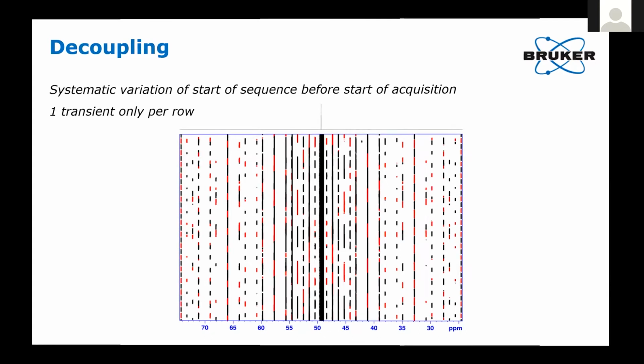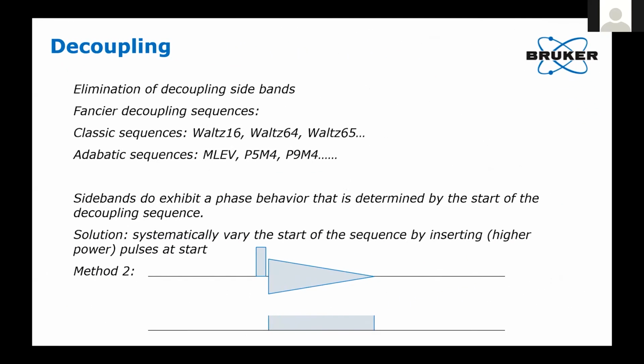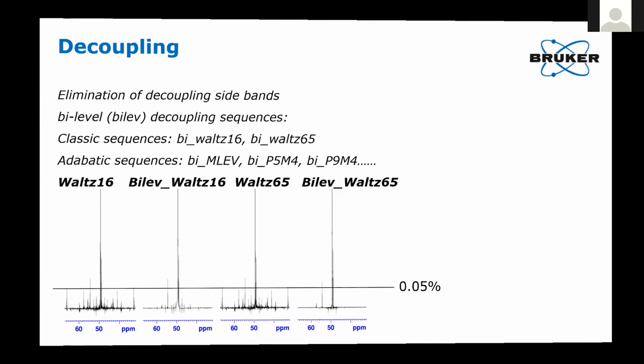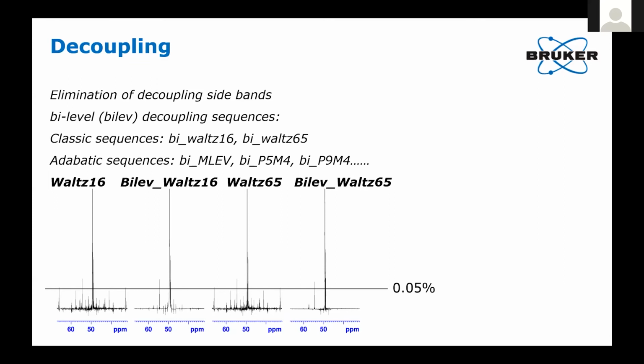The other possible approach is to shift the decoupling sequence to the right, but you can't have a gap. So what you do then is you do a series of typically higher power pulses to get a little bit of better behavior in there. And with that, you can now reach excellent performances. So again, if we start with our WALTZ-16 here, which gives us this decoupler sideband pattern, we go to a bilevel WALTZ-16, we can see that we can eliminate the lot.